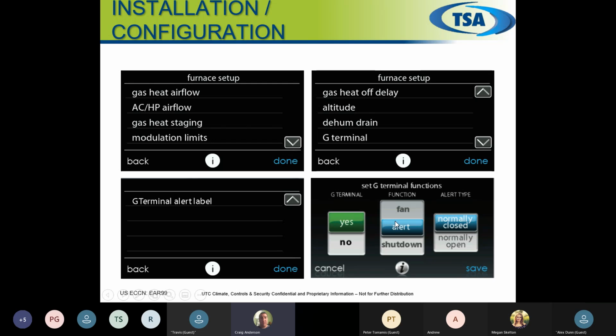G terminal setup is a big one. If you're putting an HRV onto the board, we have to energize the G. The G is not energized on the furnace till we go into the stat and energize the G. Because we're doing a fully communicating system, we're not using that terminal strip for that G terminal. So we need to go in and turn it on.